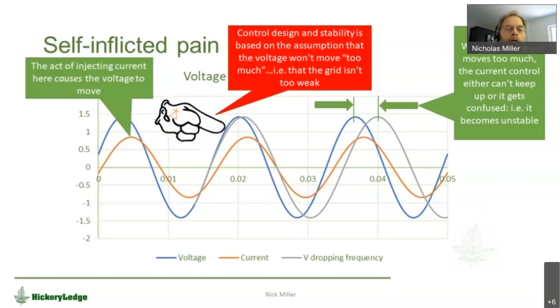The movement of that voltage is easier—it moves more for a given amount of current as the grid gets weaker. So if the grid is too weak, the interaction between the injected current and the motion of the voltage becomes ill-mannered. That's what we're worrying about in weak grids. Sorry for making that so cartoonish, but that lays out the problem.